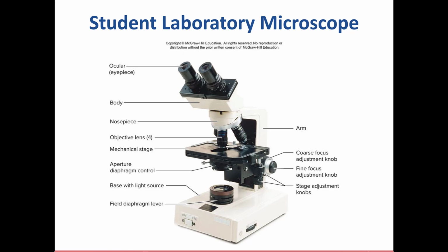And really all it's doing is moving the hardware on the surface of the stage around so you can view what's on the slide. So this holds the slide, this metal piece here. This little flange right here moves out. You have a little handheld here, and you move this out, and this will swing out. You put your slide in, and it's sprung with a spring, and that will put a little bit of pressure on that slide and hold it in place. And then you move the manipulators, and you put the slide anywhere on the stage that you want.